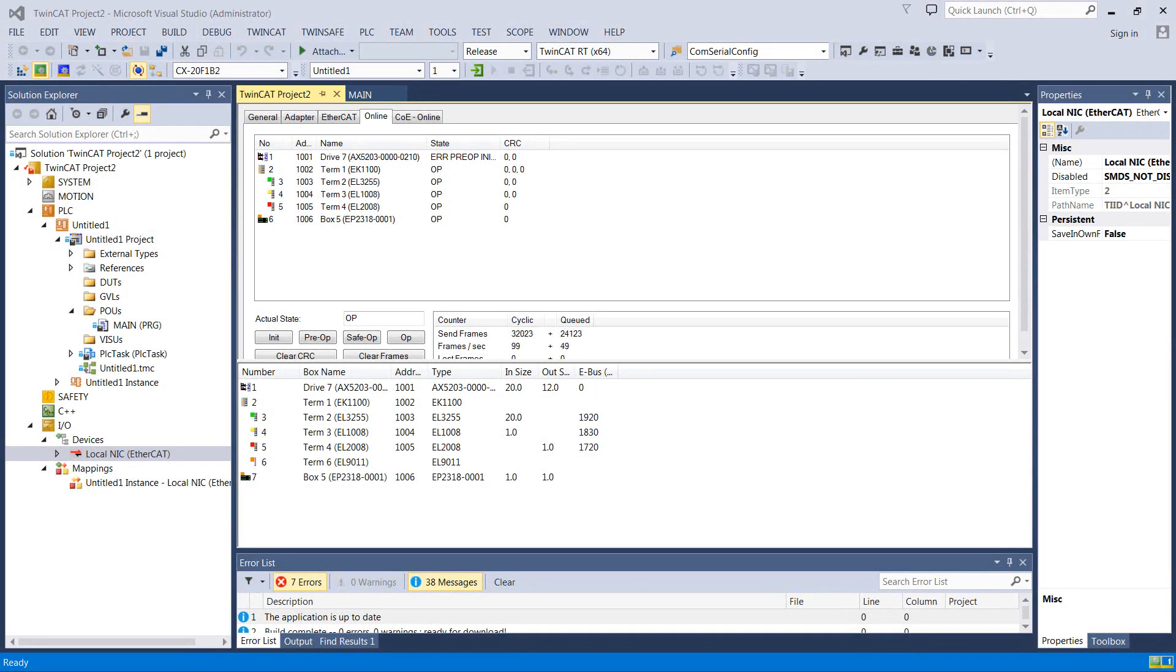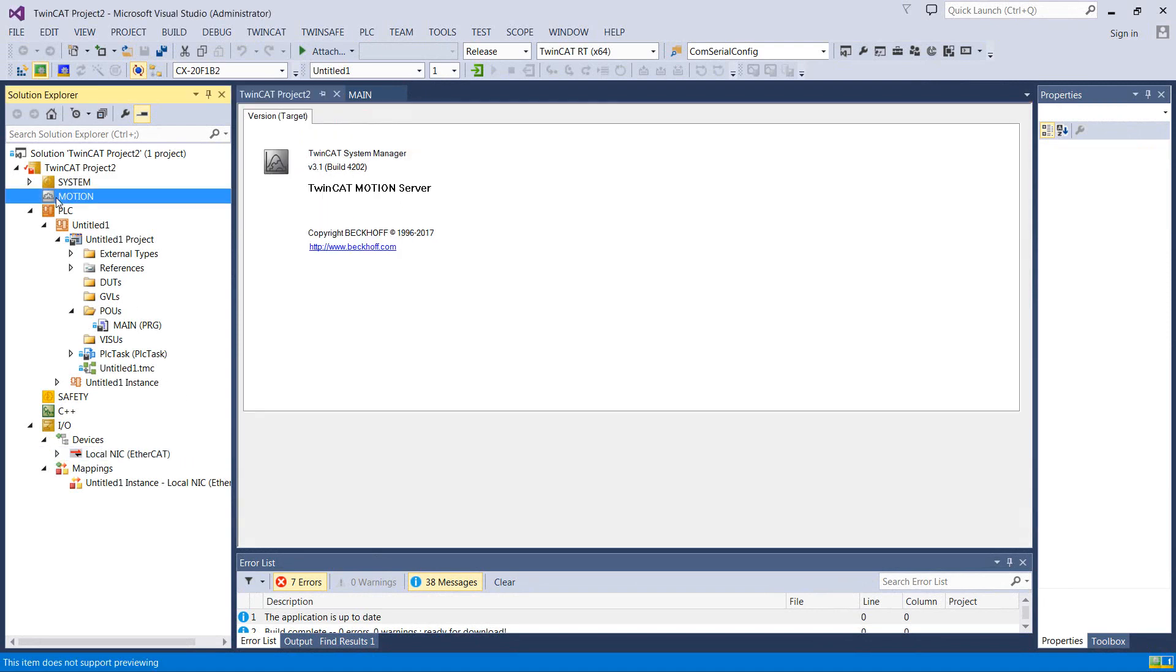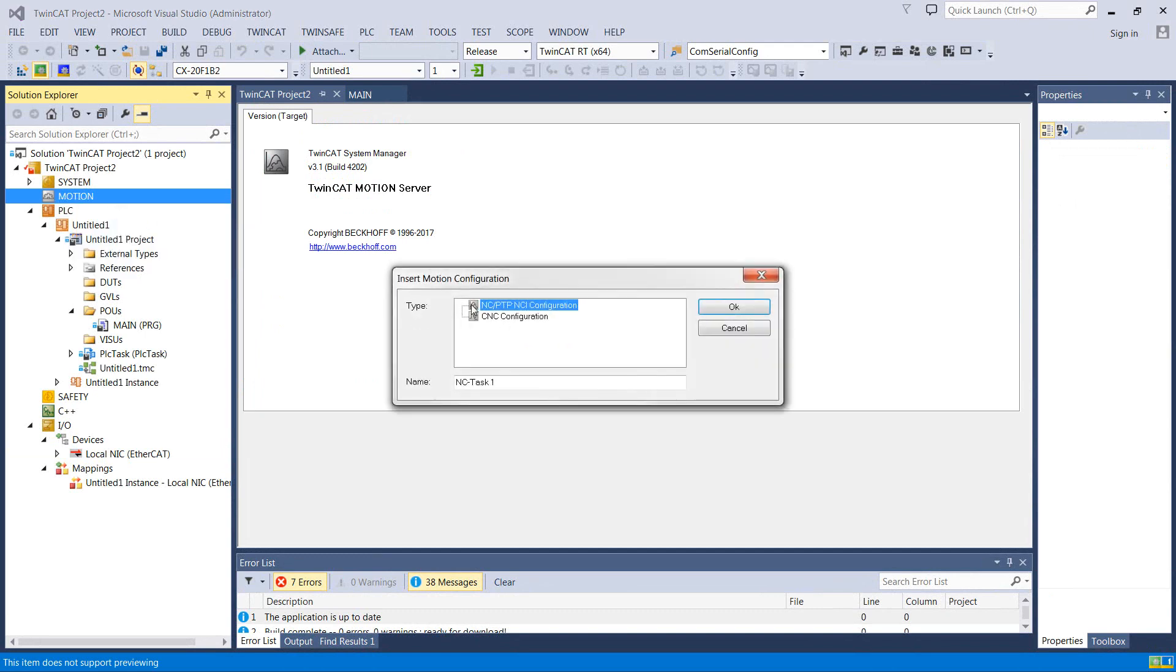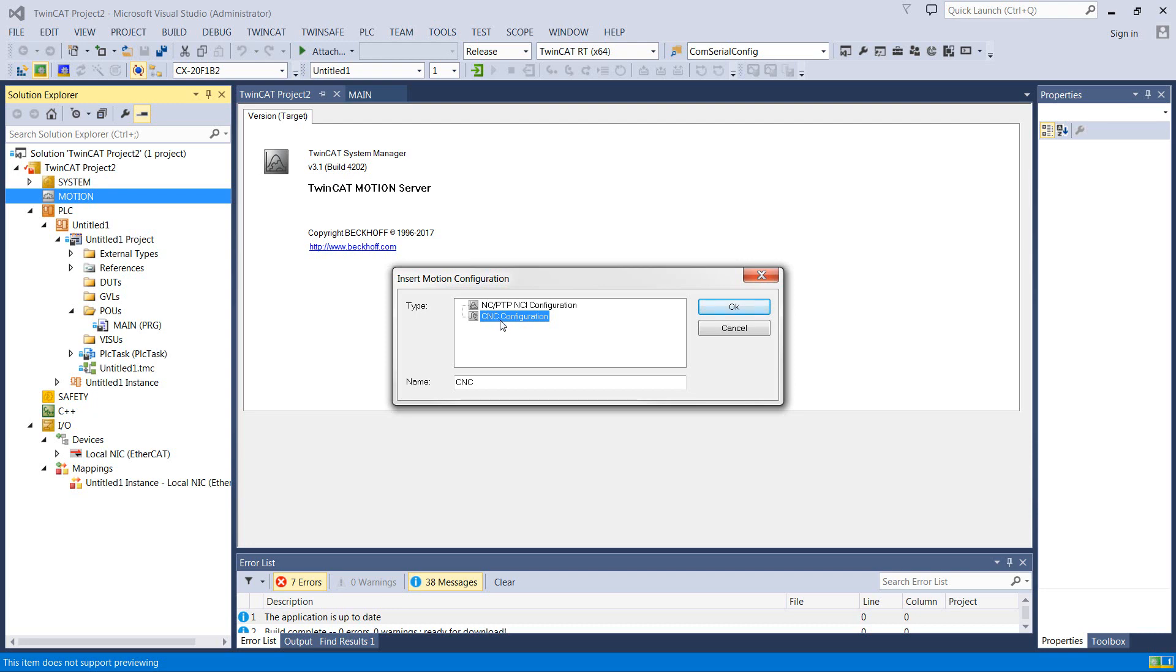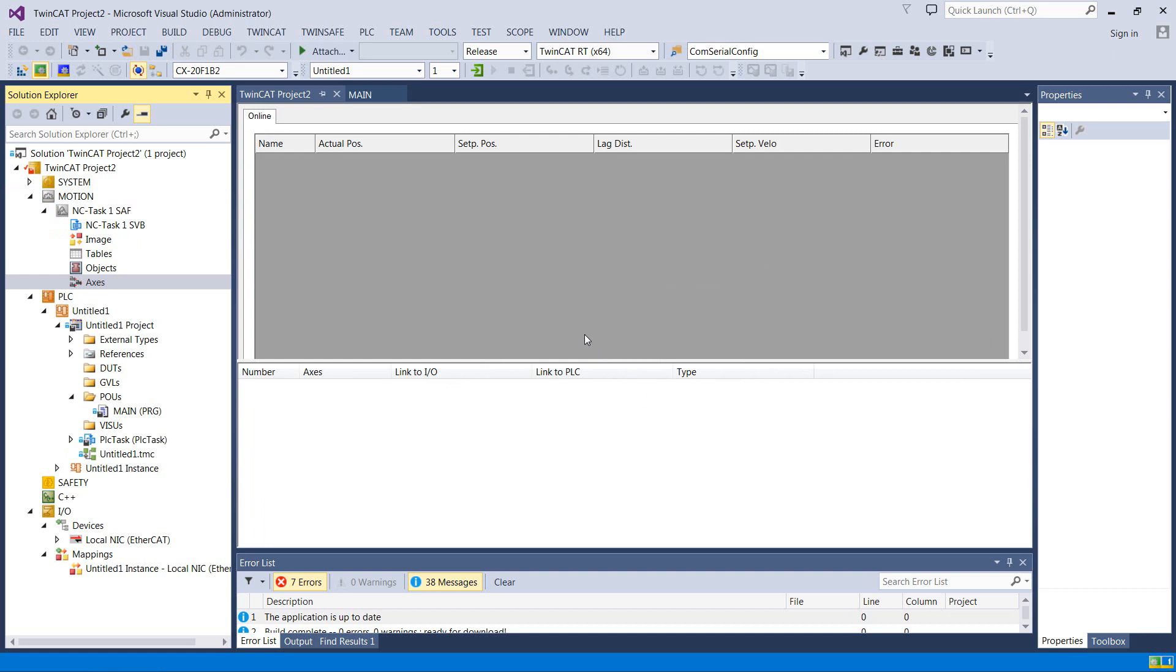All right, so in TwinCAT, we need to add an NC axis. NC stands for numerical control, and what it is is basically an abstraction layer for all the different motor types you could possibly imagine. So we'll come over this Motion tab, right-click, add new item, and we've got CNC, which we're not messing with really at all in this series. I'll probably talk about it a tiny bit later, but we want an NC or a point-to-point NCI configuration.